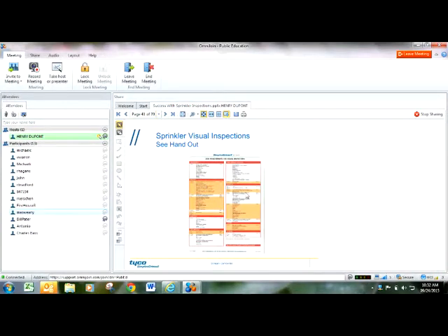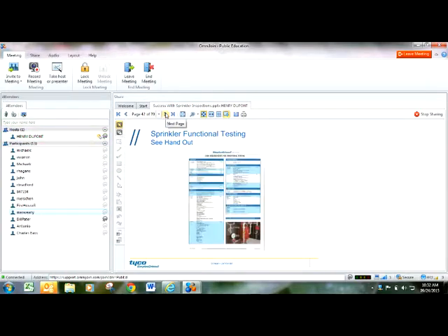Basically it's a cheat sheet of all your inspections. On this side of the page are all of the visual inspections that are required for all fire life safety systems and the intervals that those visual inspections are required. On the flip side of that are all the functional testing requirements for all fire and life safety systems and the intervals that those are required. So it's not just for sprinkler, it's fire alarm, it's kitchen hood suppression, it's sensitivity testing on fire alarm. It's just all the things that you wanted to know about inspections compressed into 1 or 2 pages. We use this cheat sheet a lot too when our inspectors are out in facilities. They'll give the facility maintenance or operations or whoever this so that they have a copy of it as well. It's a good tool to have.